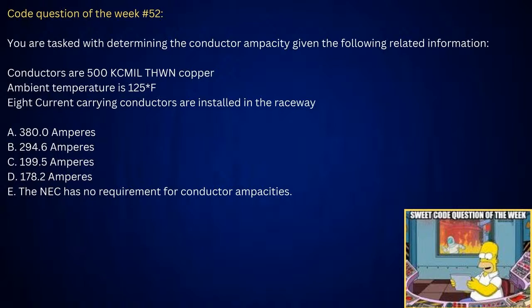Now, let me give you a little insight into what I'm talking about. If I go over and look at 110.14(C), when you pick up 110.14(C), I'm just going to read the last sentence in the first paragraph there. I'm not going to look at (C)(1) and (A) and (B). I'm just going to read the temperature limitations. It says, conductors with temperature ratings higher than specified for terminations shall be permitted to be used for ampacity adjustment, correction, or both. Now that's interesting, because it says temperature ratings higher than specified for terminations. So I can have a 75 degree C termination here, but in order for me to use the 90 degree C, I would have to look at 310.4 and my type of conductors. So if I had THHN here, I could use the 90 degree C. If I had THWN-2, I could use the 90 degree C.